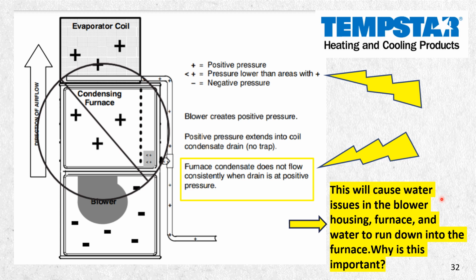Now, this is something we've seen in the past. Why the UV light came out was to kill mold and mildew that was caused by water in the evaporator area or in the coil area getting on the insulation and growing mold. All due to the water being left in the trap, and if the trap is full, where's the water going to go? The blower motor is going to suck it all in and blow it all through the unit. So you got to keep that in mind. When I get that condensate drain, the drain's got to always stay flowing and empty.